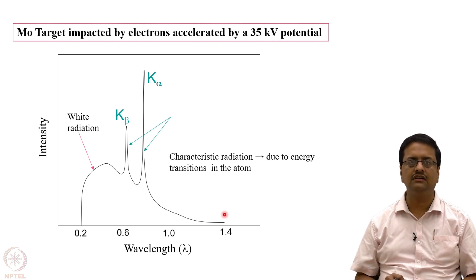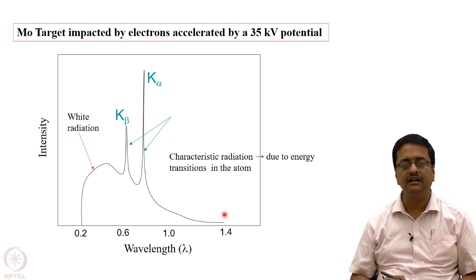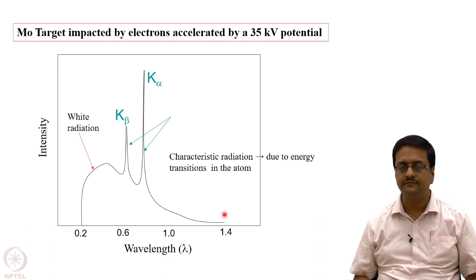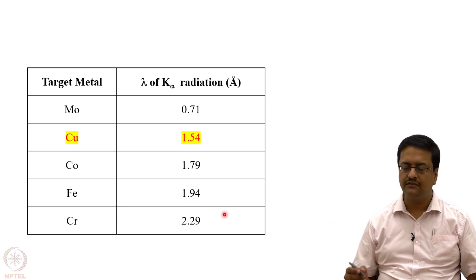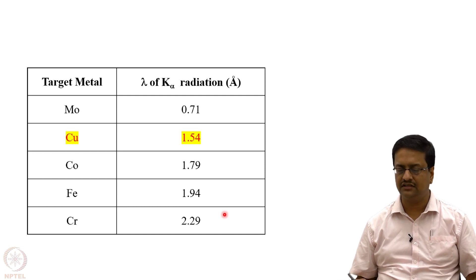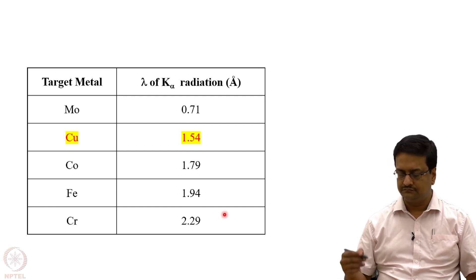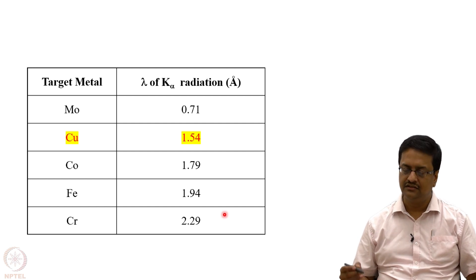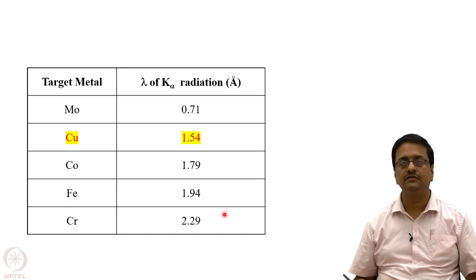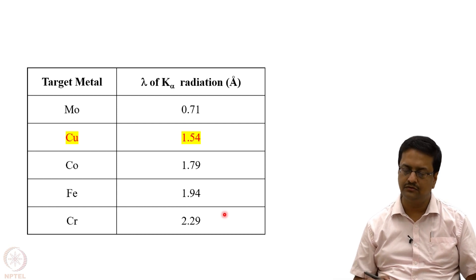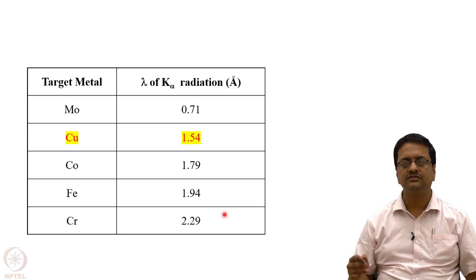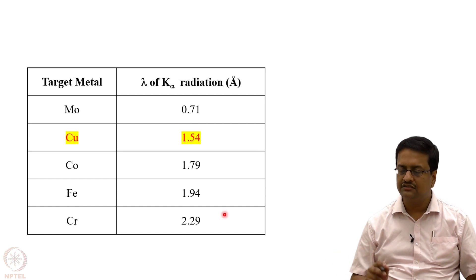In general, for all X-ray diffraction purposes we use K-alpha radiation. As you already know, there are different metal-based sources used for X-ray diffraction: molybdenum, copper, cobalt, iron, chromium, and nowadays silver-based sources as well, with wavelengths varying from 0.71 angstrom to 2.29 angstrom. The most widely used radiation is molybdenum for single crystal X-ray diffraction, while copper X-ray is used mostly for powder X-ray diffraction because of its larger wavelength.